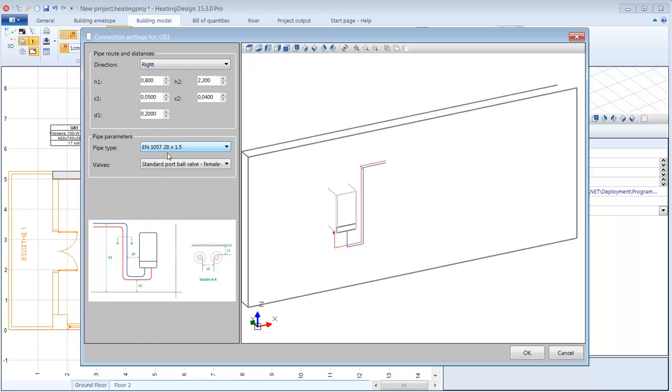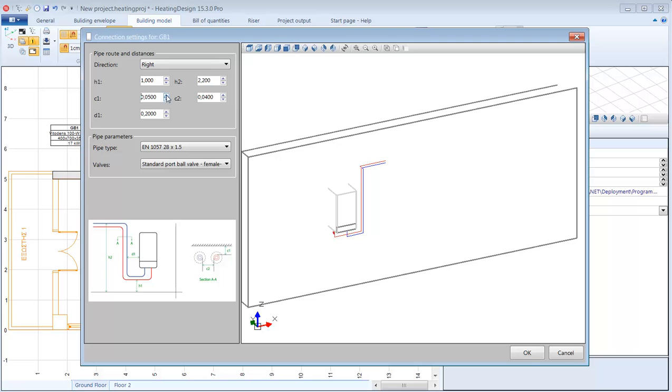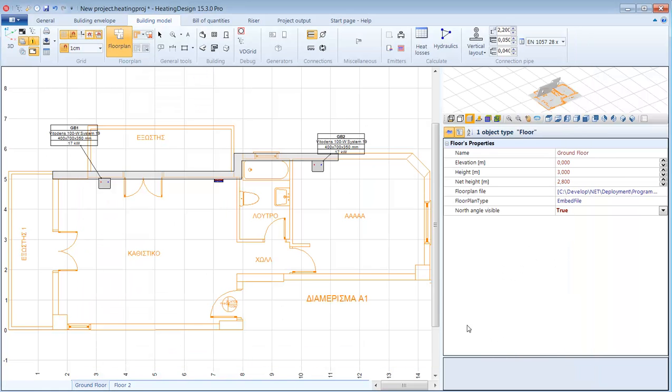I will run the pipes at 1 meter height and then they go up to 2.2 meters. And I will set the distance from the wall to be 3 centimeters. Of course for this distance I will have to take into account the pipe's insulation. So after I click OK, the pipes have reached the point that I specified and I can continue to run the pipe to finally reach the manifold.